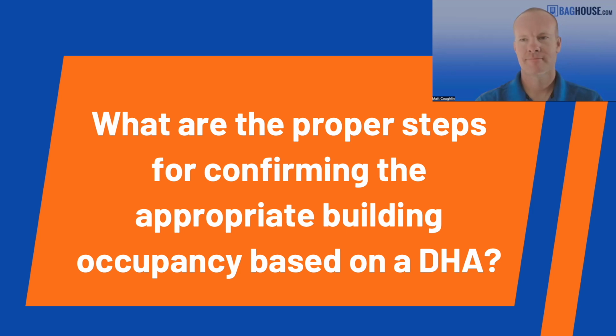So the answer that I was able to find, and I'm getting a little outside of my experience here, is basically that the presence of combustible dust in the facility is not alone enough to trigger an H2 classification. It depends how that combustible dust is mitigated. If you have combustible dust in your facility and you have added explosion vents, isolation, suppression, all the stuff that the NFPA guidelines tell you to do, you should be able to avoid the H2 classification, because basically it says that you have combustible dust, but you've mitigated the risk.